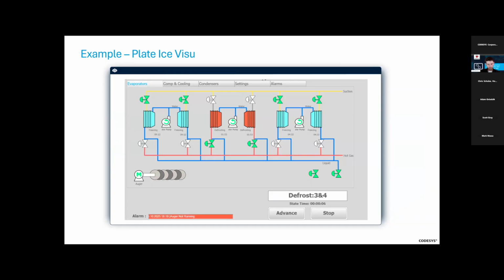But as you see here, we're defrosting 2 sections at a time, and this is important for balancing our compressor load. We always want to have a certain amount of load so we can maintain that head pressure to have that hot gas for a defrost. We have some scenarios where we run individual machines and we need to add a false load just to keep those pressures up so we can get that ice out.